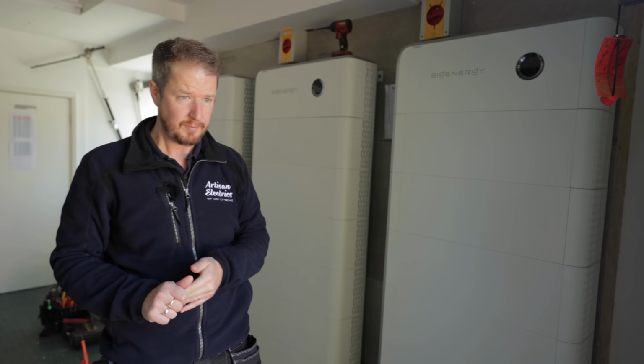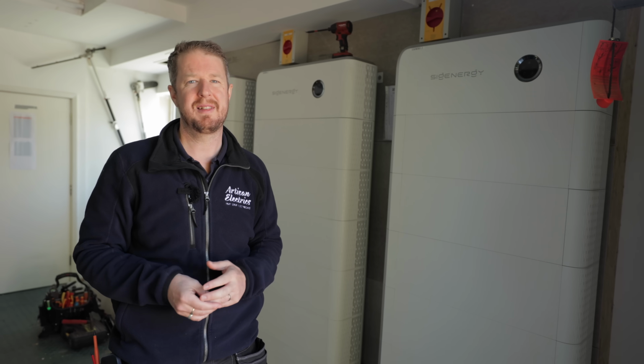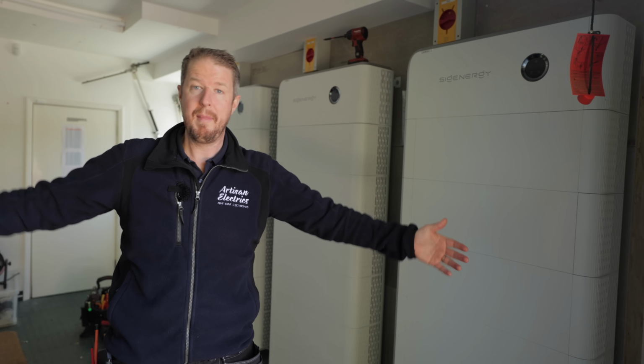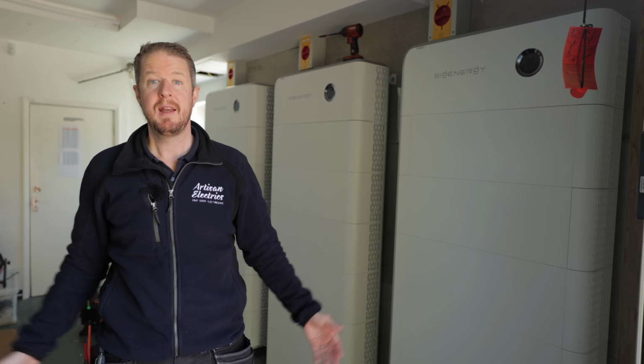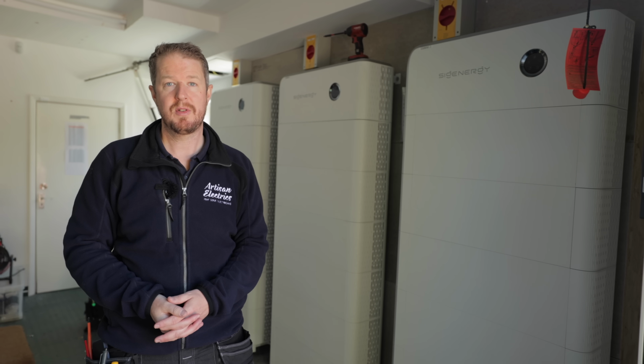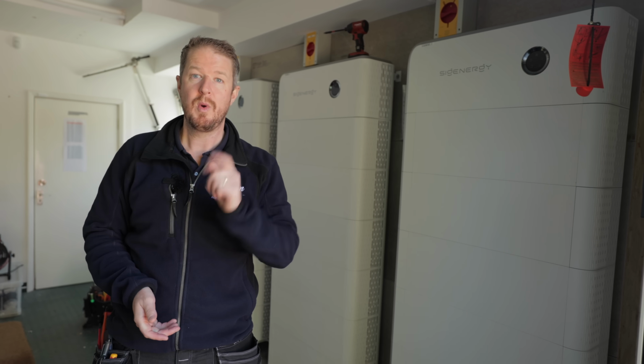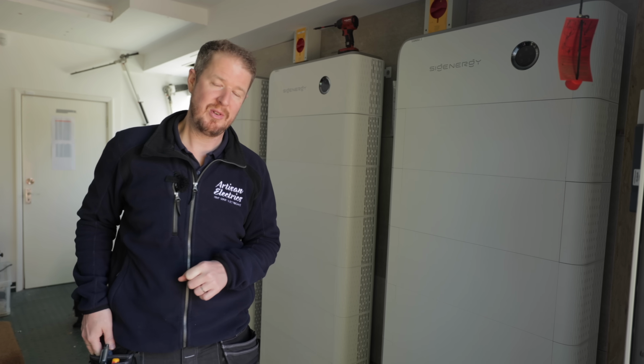Now, there are smaller, more compact systems out there, but in general, I'd say most people do need at least a 1 meter by 1 meter space in order to fit a reasonable battery storage system in place. And what I would say is you should never install batteries in lofts - that's a guideline from the PAS 63100 document as well.